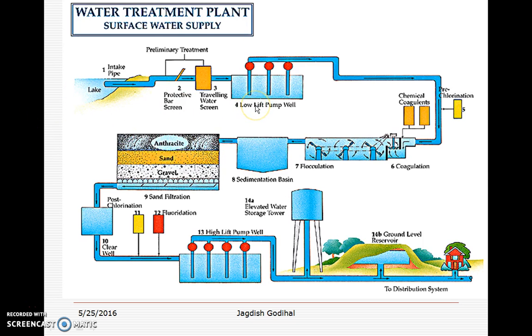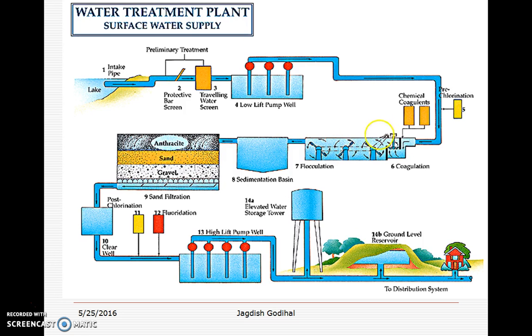The goal is to make the raw water into potable water. To ascertain the function of each unit of treatment — for example, sedimentation, coagulation, and filtration units — we have to have monitoring points at both the inlet and outlet of each unit. In the coagulation unit, for instance, we are removing colloidal particles. If we know the concentration of colloidal particles entering and leaving the coagulation tank, that gives us the efficiency — whether the plant is working at its design efficiency or not. Water quality parameters play an important role in the performance analysis of each individual treatment unit.